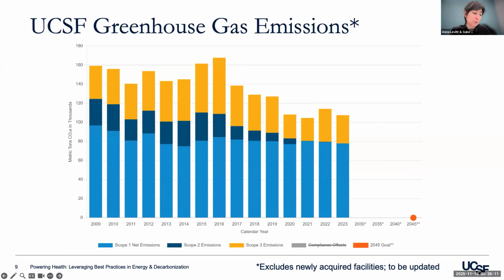That plant is both our greatest challenge and our greatest opportunity from a decarb perspective. It provides wonderful electrical resilience and serves a steam network that would need to be replaced. We're not as far along as some other UCs in advancing this, but we're carefully examining how to transition from that steam distribution network to an electrified heat recovery chiller-based system.